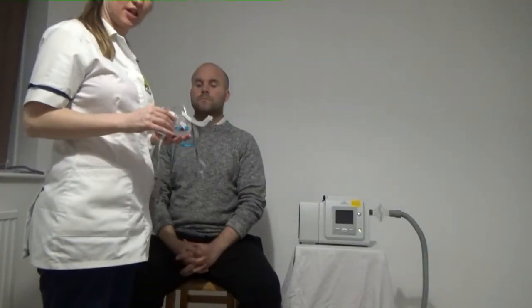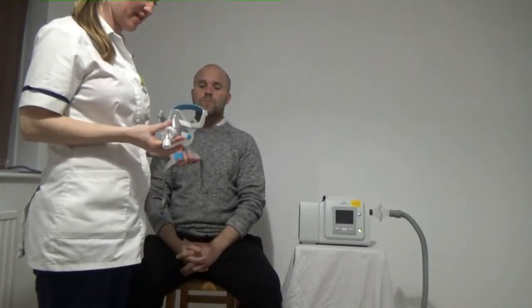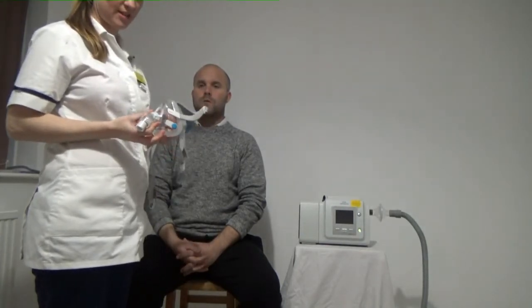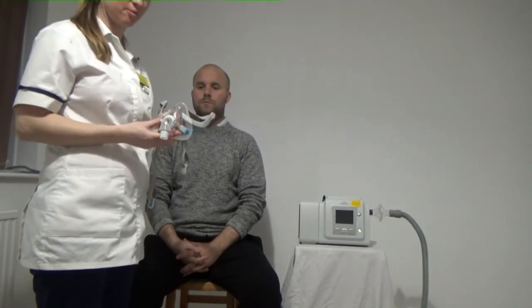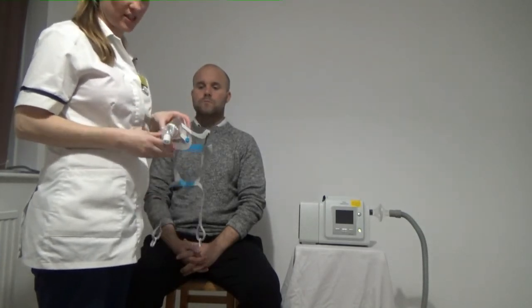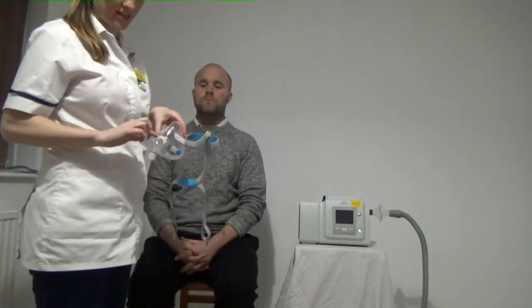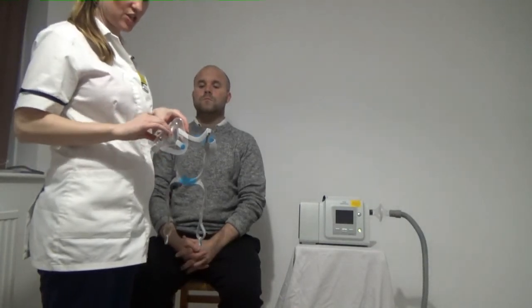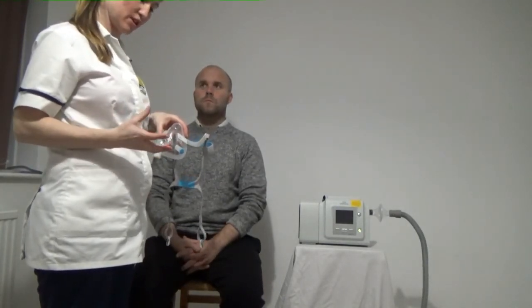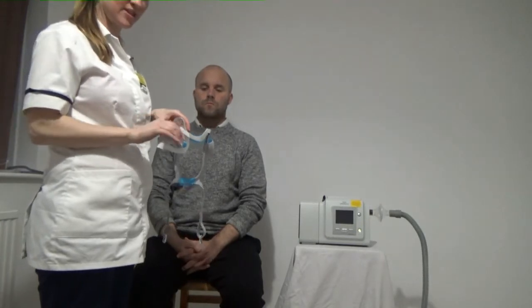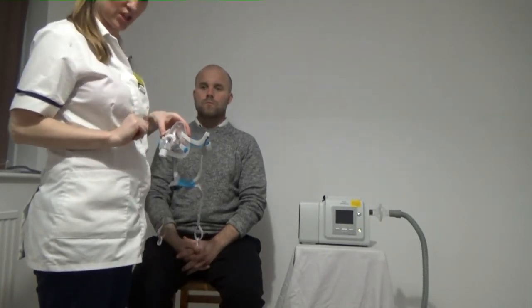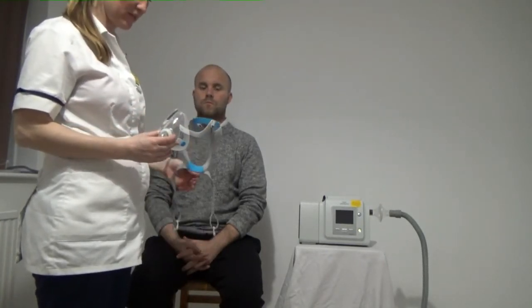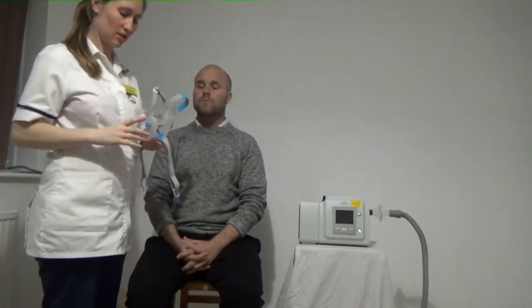There are 4 main types of masks that you can use with NIV therapy. This is called the full face mask and fits over both the nose and the mouth and is particularly good for mouth breathers. It is worth noting that the expiratory port is around here. This is an intentional leak that allows carbon dioxide to escape. It is important that this is not covered over, for example with bed sheets, whilst your client is in bed. To fit this mask, the lower part of the mask sits between the chin and the lip and the upper part sits on the nose.